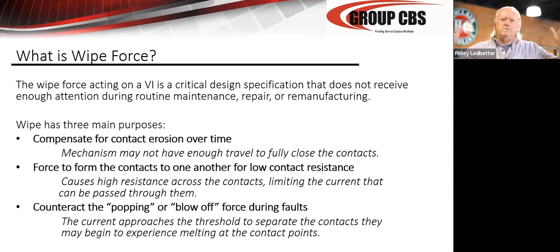Think about a dry type transformer, a big dry type transformer, 3,750 kVA, 15 kV class transformer. It's designed to be hit on all three phases simultaneously so the magnetic stresses don't damage it. If you get single phase or you hit one phase before the other two, the whole core tries to twist and you damage the breaker. Excuse me, you damage the transformer. So popping forces cause that. So it's very important to maintain proper pressure.